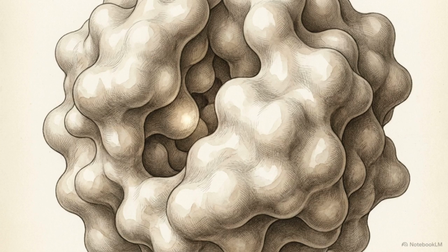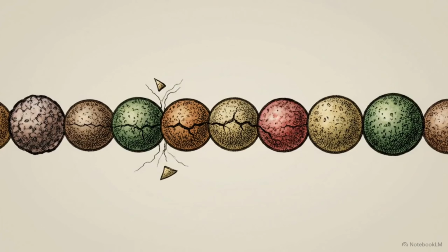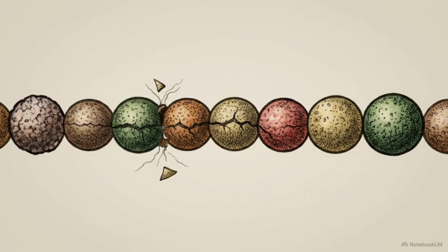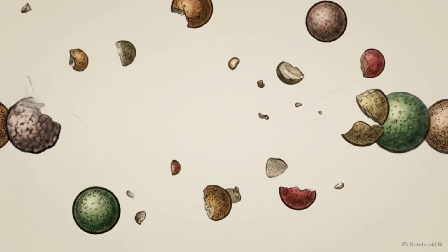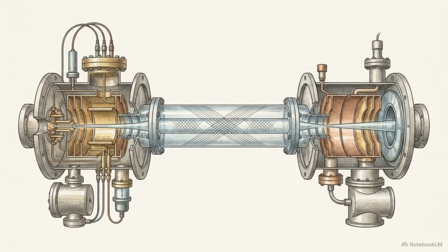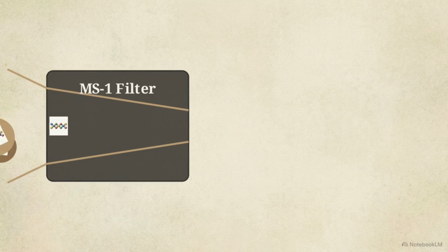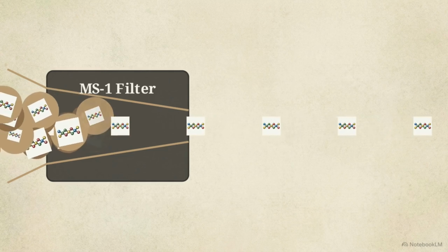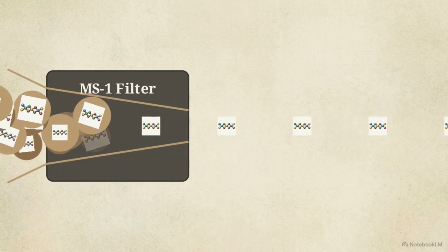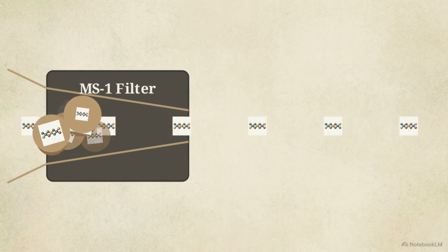These isolated peptides are then fired into the collision cell, a vacuum chamber bled with a tiny amount of a noble gas, like argon. The physical impact between the high-speed peptide and the static gas particles fractures the molecule. Due to the physics of the collision, the breaks occur almost exclusively at the peptide bonds, snapping cleanly between individual amino acids. Crucially, the electrical charge from the original peptide is retained on only half of the newly created fragments, either the amino terminal side or the carboxyl terminal side.